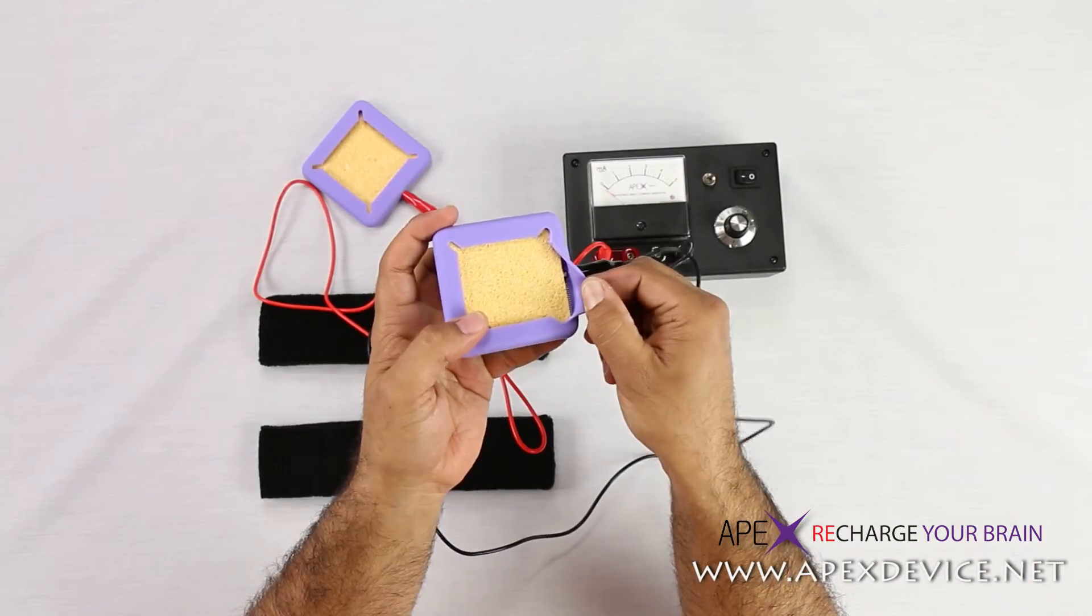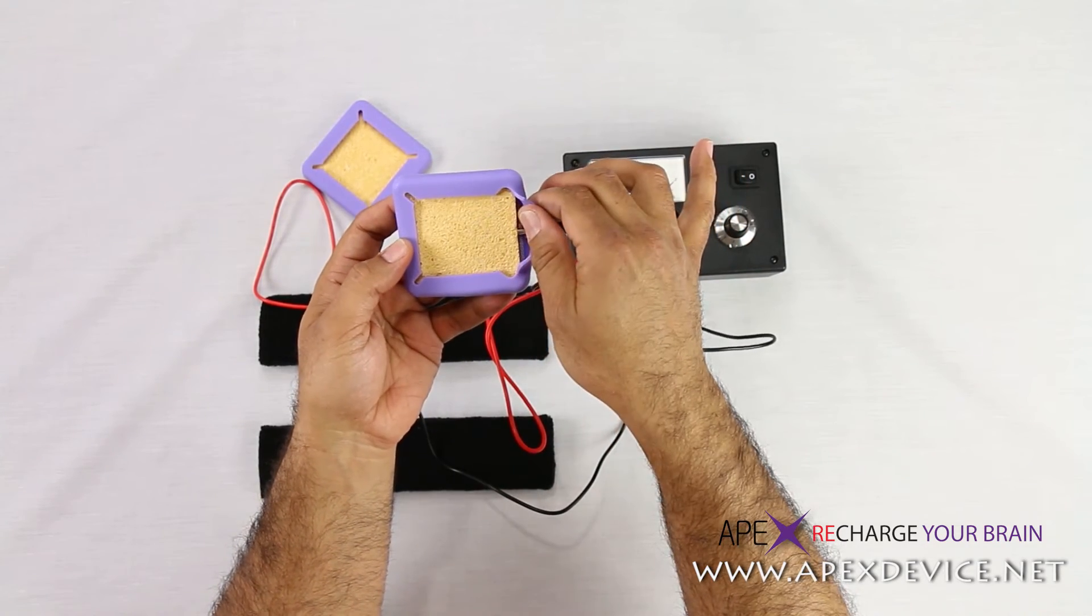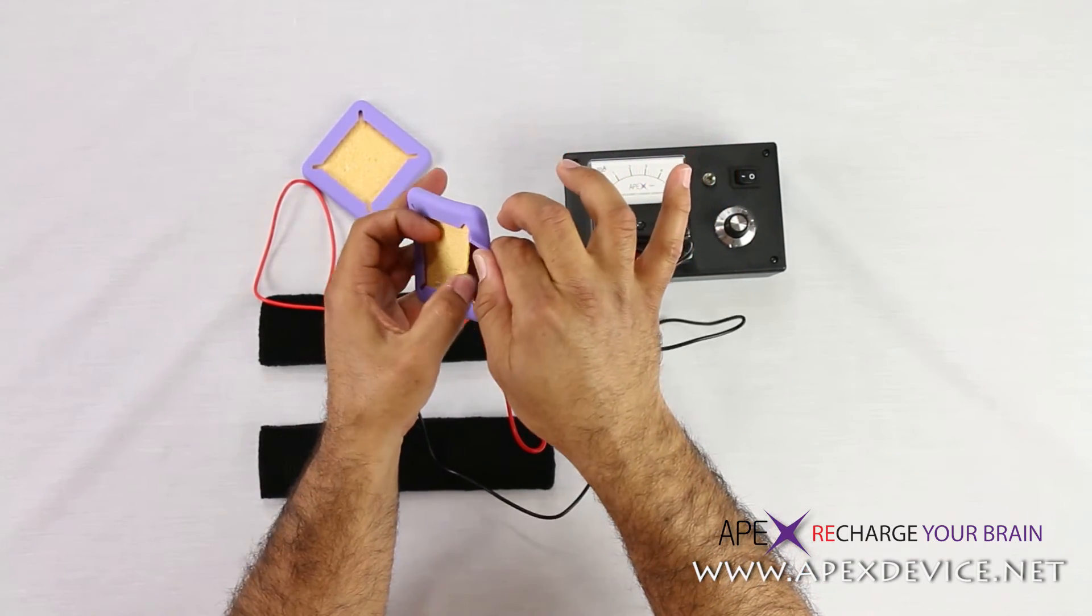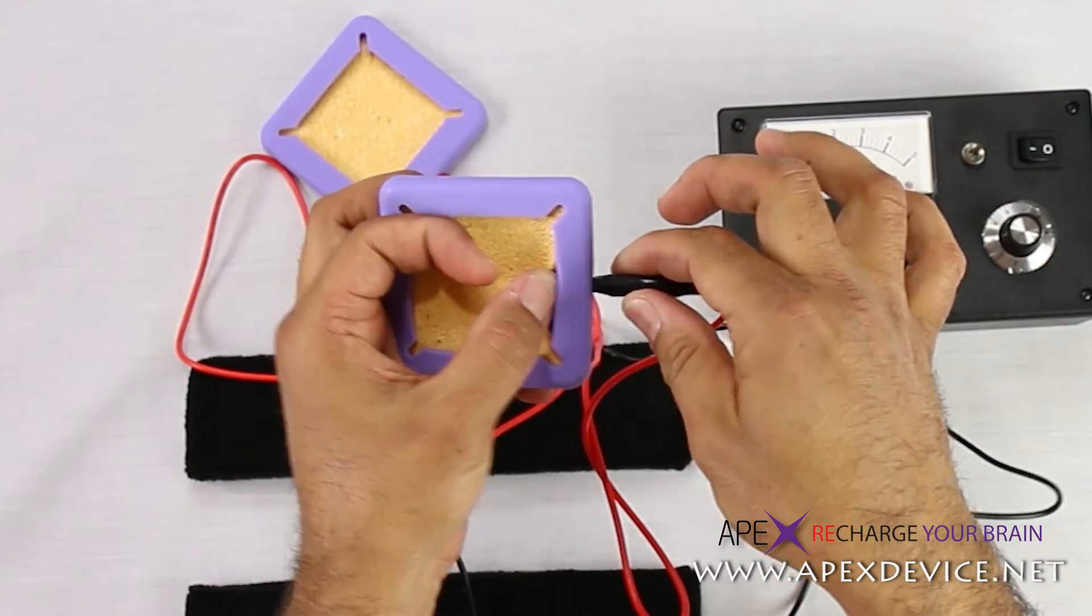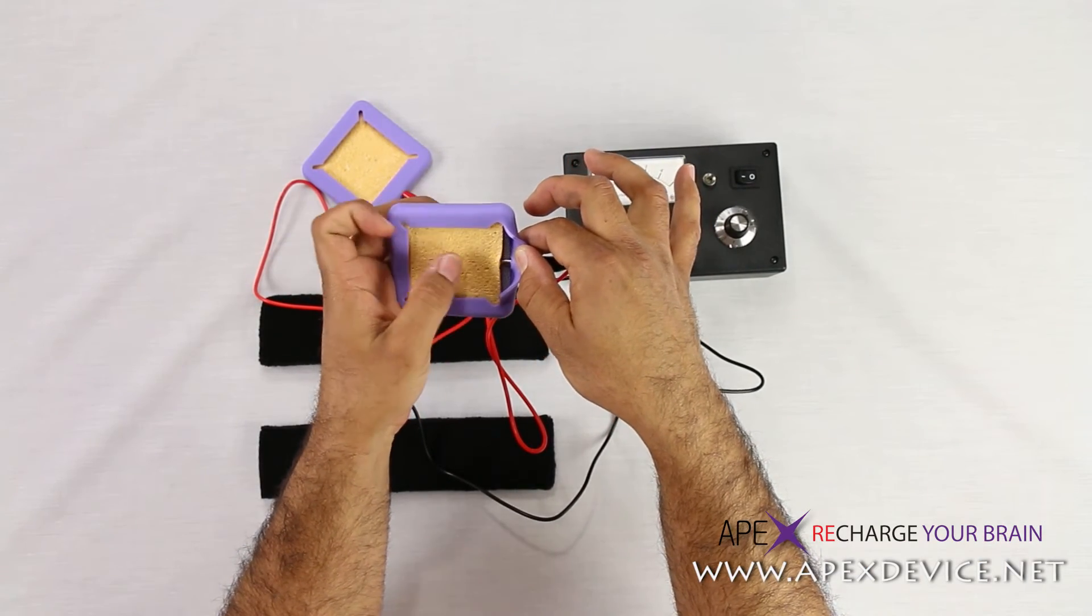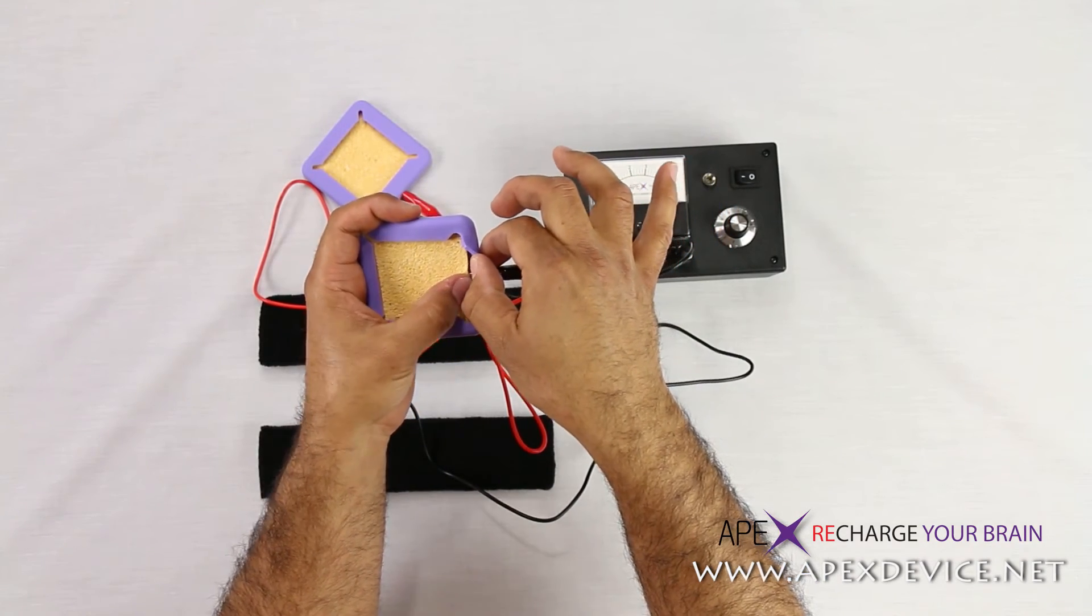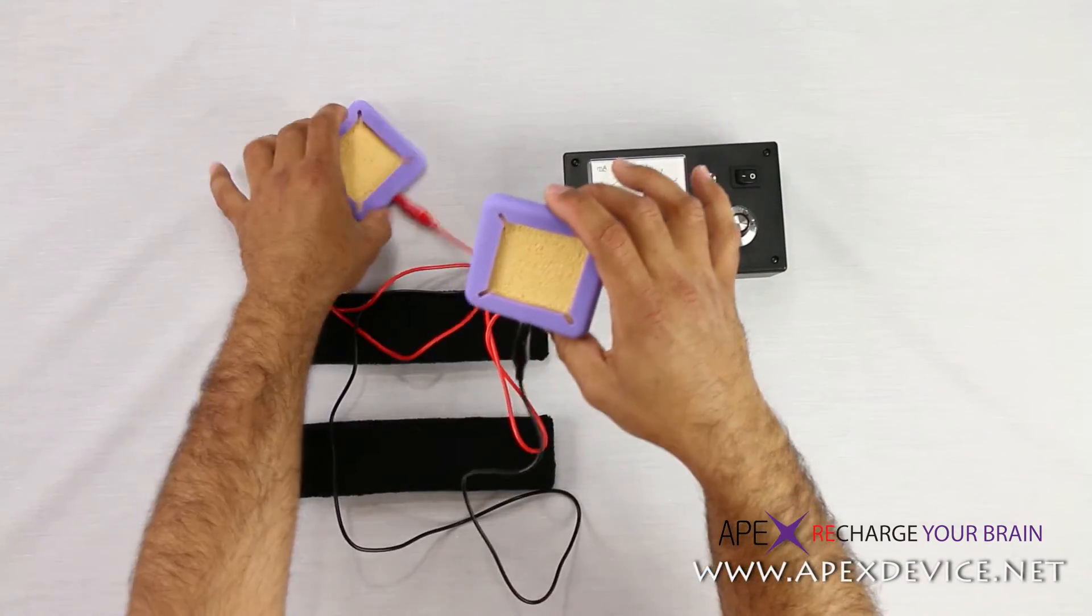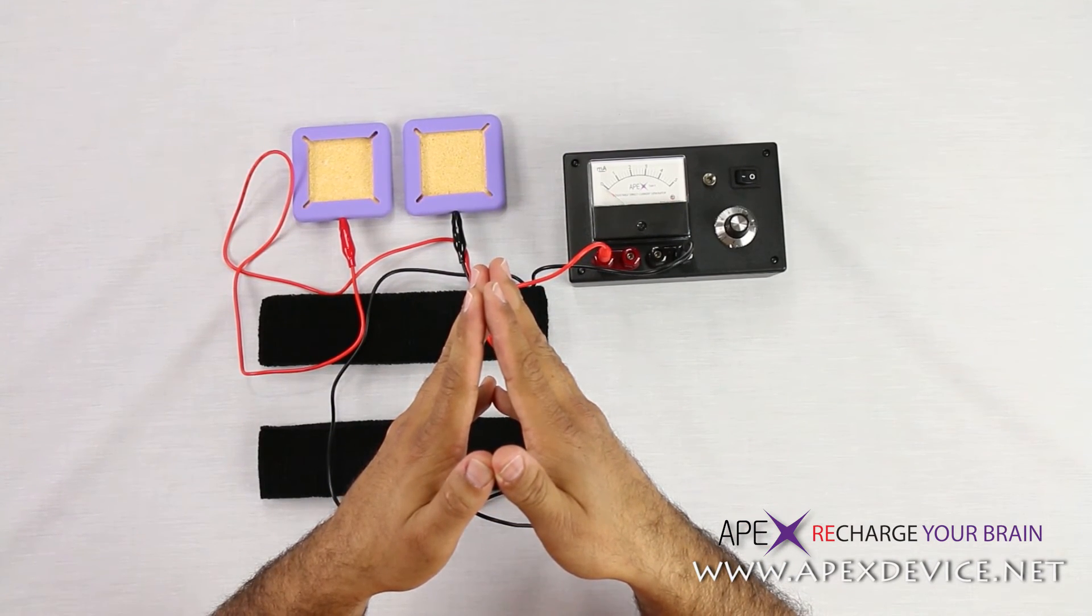Let me unspin it. And you can see how easy it is for the electrosquare electrodes. They're made out of this soft silicone material that's hard enough to keep its shape, but it's soft enough that you can pull it up very safely. So you can pull it up and you can inspect the element right in there. It's grabbing that very nicely. No danger at all. And you're going to cover that up. Another thing you want to make sure is that metal stays underneath the silicone, underneath the sponge. Don't grab the sponge. Basically keep it right in there. Once you have that on, all you need to do is pour some water on it. And this sponge is going to expand and it's going to allow you to perform the stimulation very safely.